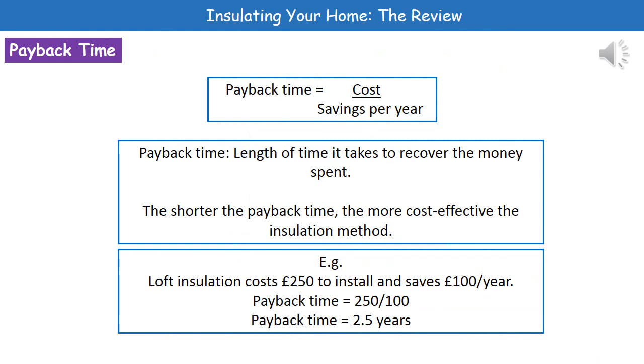Last thing we need to consider is something called the payback time. This is basically the calculation you should do to work out if an energy saving method is worth doing or not. To calculate payback time, all you've got to do is the cost of the installation divided by the amount you save per year. And this will then give us the length of time it's going to take to recover the money we've spent.